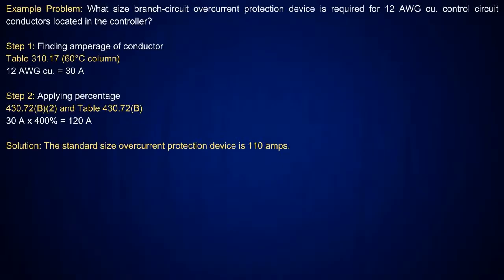All right. And the next one we're going to look at is control circuit conductors. Now, this particular one is where the conductors are located in the controller. And remember what I said when we were doing this. This is a verification for when you go look at 430.72(B)(2). And I said when you're in there, below the table you're going to have your notes, where all this ties in together. Basically, since you're inside the enclosure, I said you're going to be looking at table 310.17 because that's considered to be free air space.